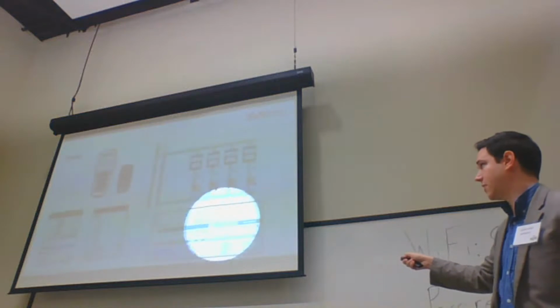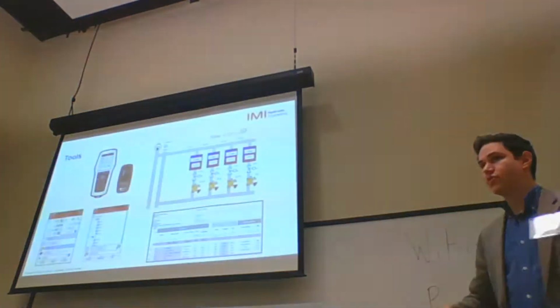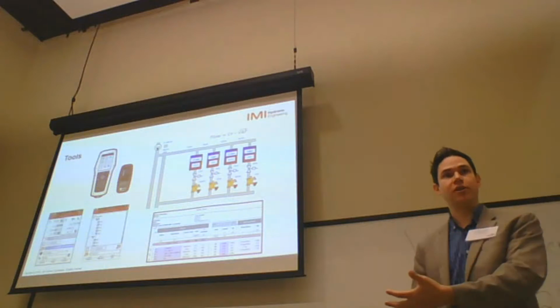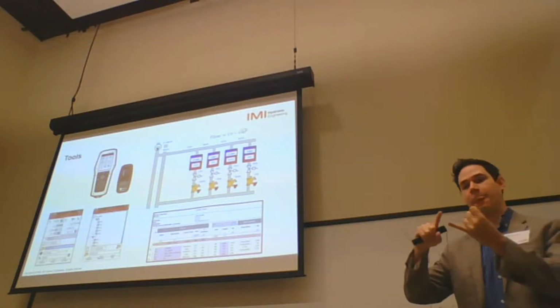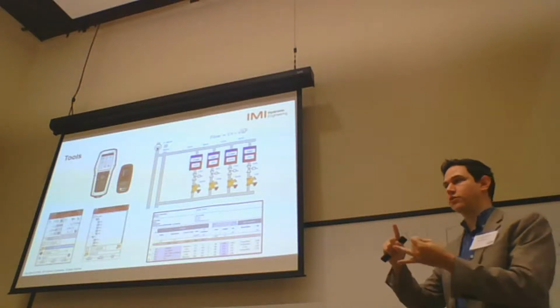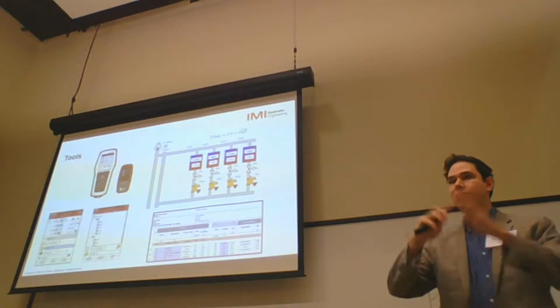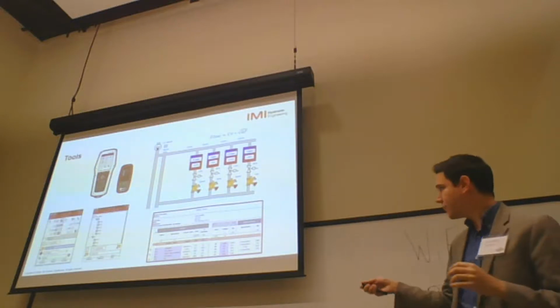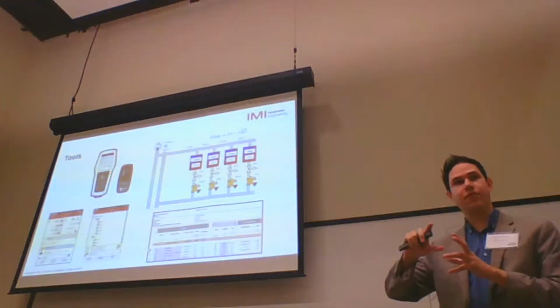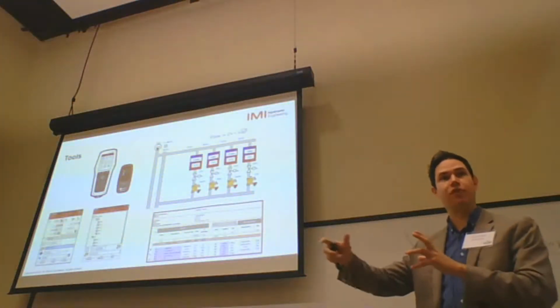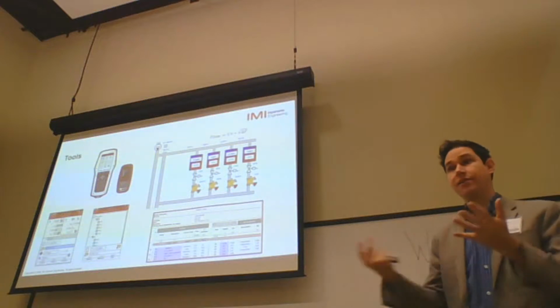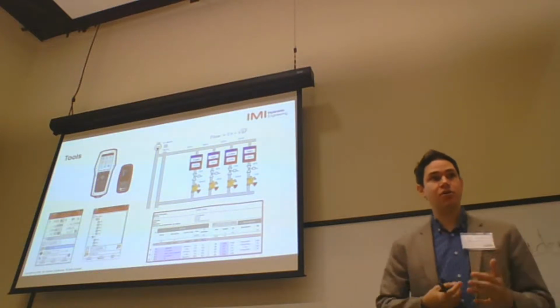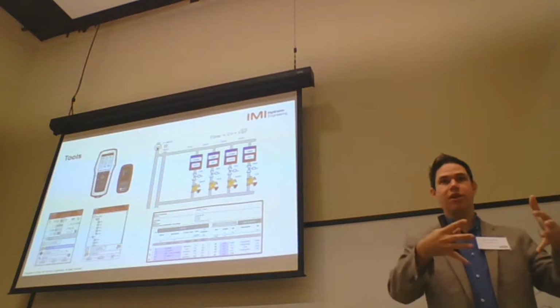The first one that I'm going to talk about is this one on the bottom right. This is software where you can input the whole project, all the pipe lengths, the pressure drop of the coils, elbows, all the accessories that you have in the whole installation. And the software basically gives you all the balancing valve positions. What is the set point for each balancing valve? And it is free software, by the way. So you can just input all the project information.